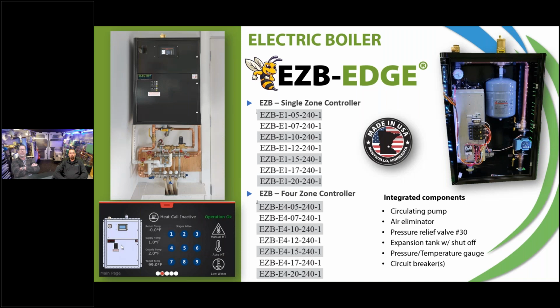The largest unit, 20 kW, is roughly 68,000 BTUs, which covers a good chunk of most people's homes. I pitched this yesterday on a radiant design—did a walkthrough, they wanted me to look at the boiler. They built a thermos of a house, spray foam insulation, and had a gas 250,000 BTU boiler in there. I did a load calculation and it came out to maybe 48,000 BTU. People don't trust the numbers, they look at what's already there. The whole approach is you need to get comfortable understanding what was said earlier.